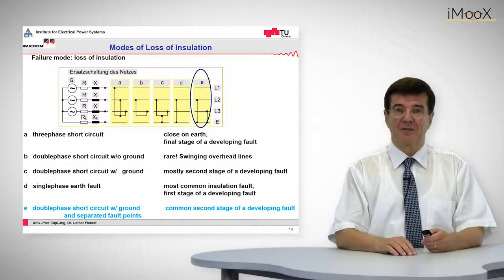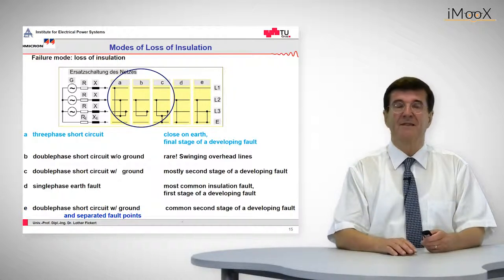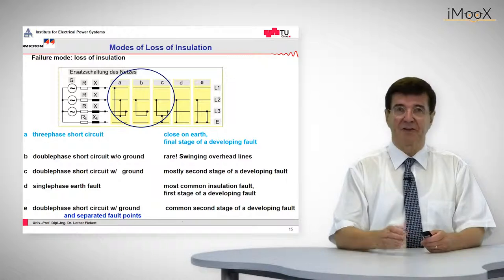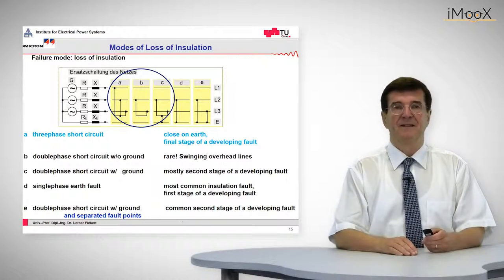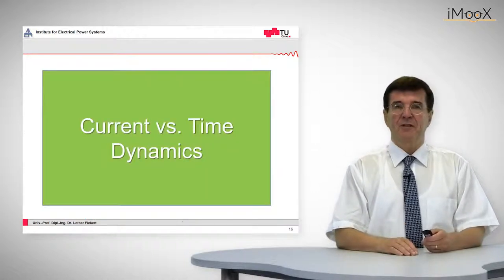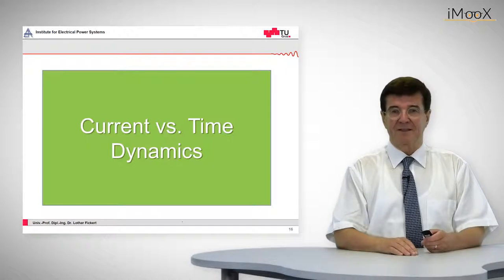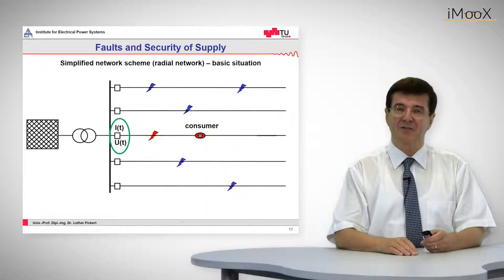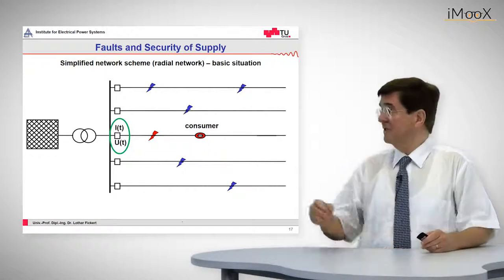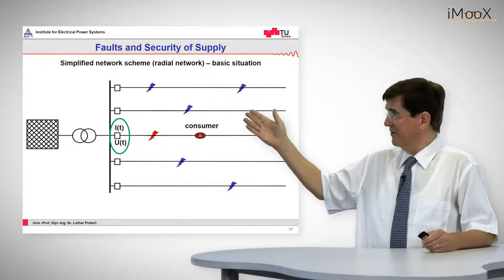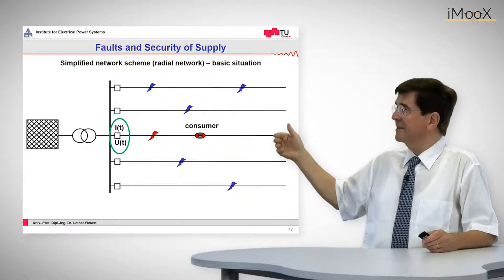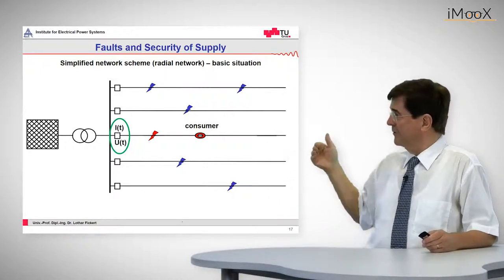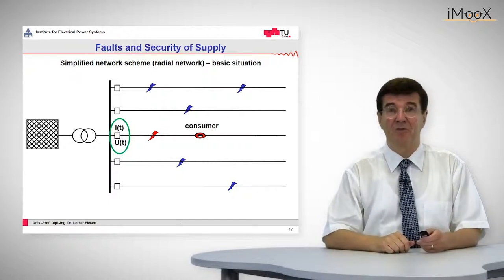In overcurrent protection I would like to deal with the typical short circuits — that is phase to phase, between three phases, and so on. First we look at the current versus time dynamics. Let's start with our standard grid which was already introduced. This is a radial grid. From left to right we have a grid, a transformer with a bus bar, a metering device given in green, and we have the line with the consumer where this fault will occur.